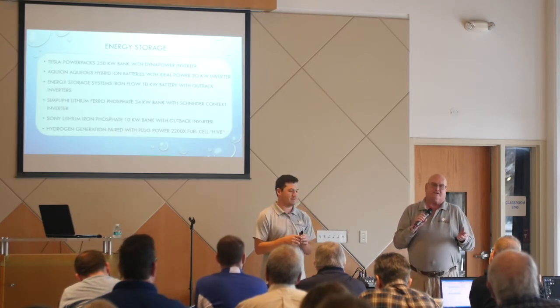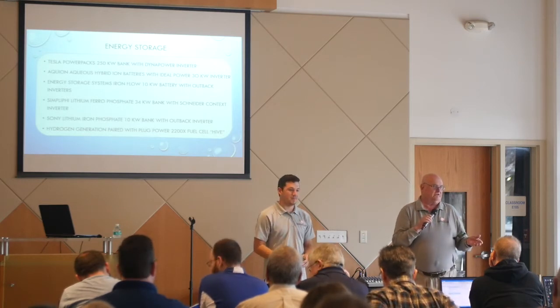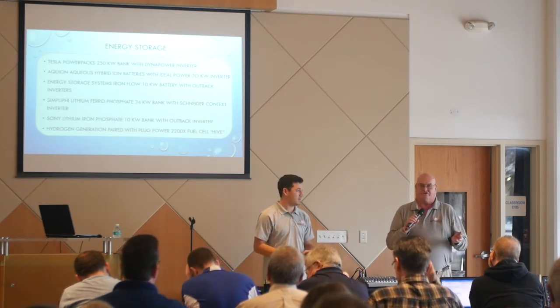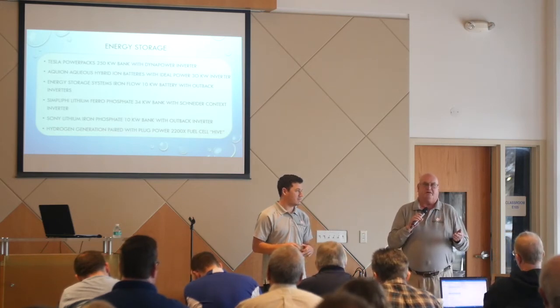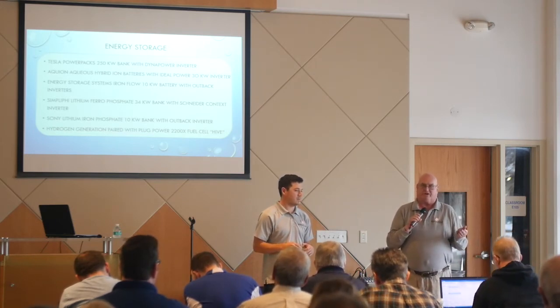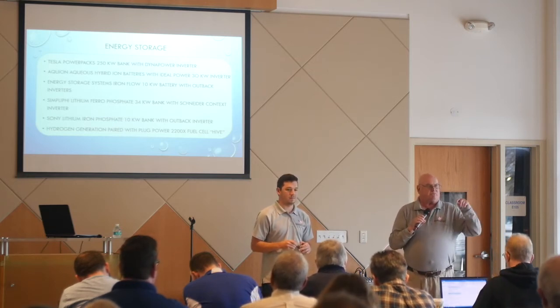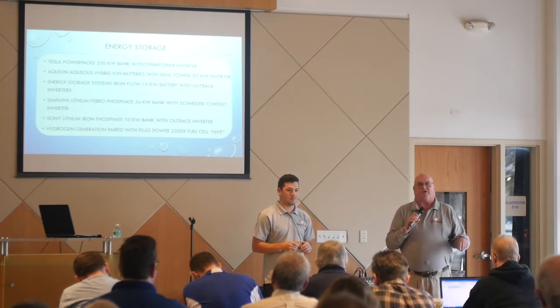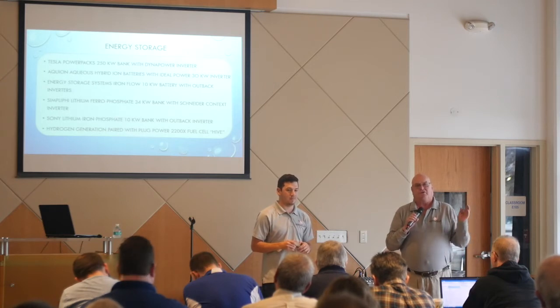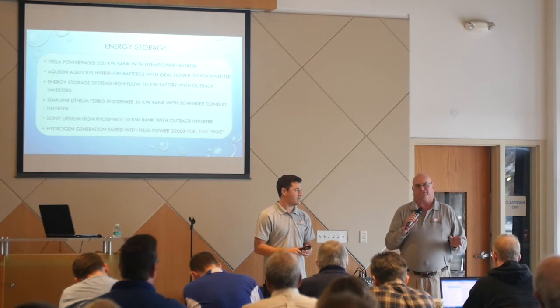One of the things I really want to look at, as we switch our Capstone over to operate on hydrogen, we were originally doing this in conjunction with UC Irvine, who has already done that. They wrote a white paper on it that's available, open source, to anyone who's interested. Right at this very moment, Capstone and Argonne Labs are working on a joint project funded by the Department of Energy to retrofit a Capstone generator to run on pure hydrogen gas.